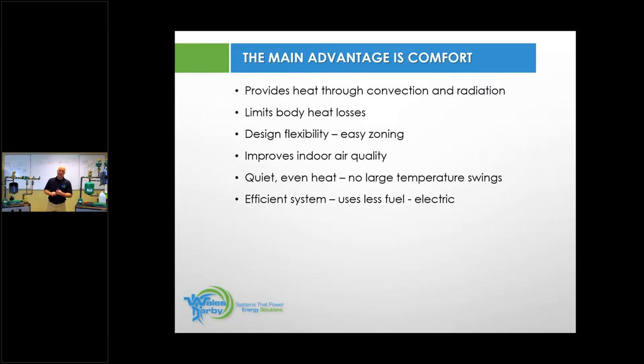Quiet, even heat, no large temperature swings. With the technology that's out there today, with outdoor reset, whether it's a cast iron boiler or a condensing boiler, we have the capability to put outdoor reset on there. So if you have those expansion creaks going on in someone's home, we can make a nice, quiet, even heat system across the board here.